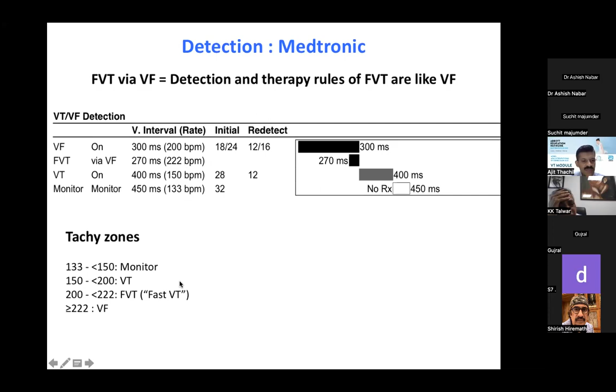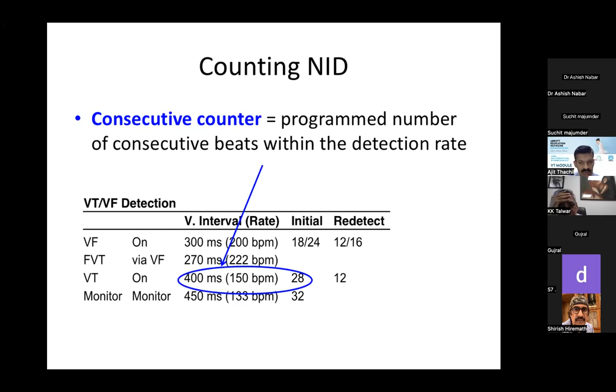So this counting is called a consecutive counting. It's self-explanatory. The program number of consecutive beats within the detection range, which should be reached to diagnose a ventricular tachycardia. Whereas this is called a probabilistic count. That is, see, here there is ventricular fibrillation going on. These wavelets are too small to be sensed.